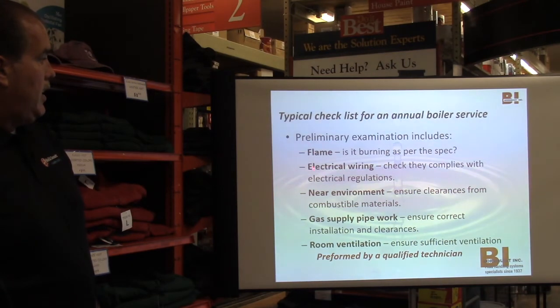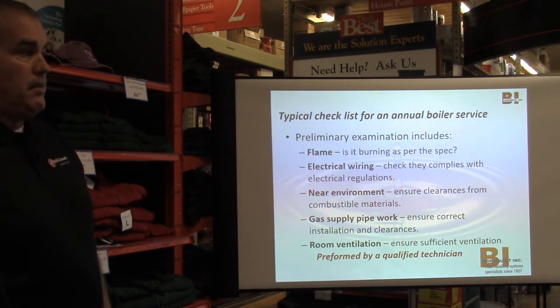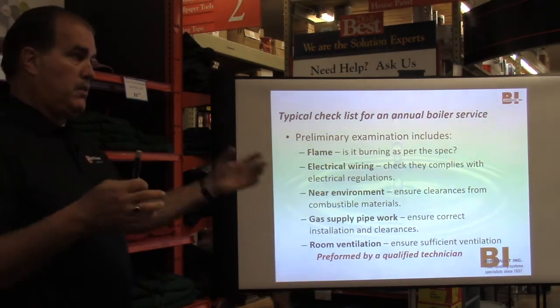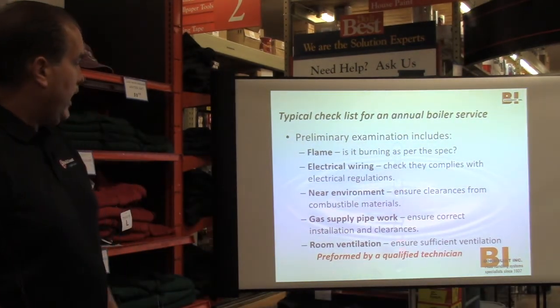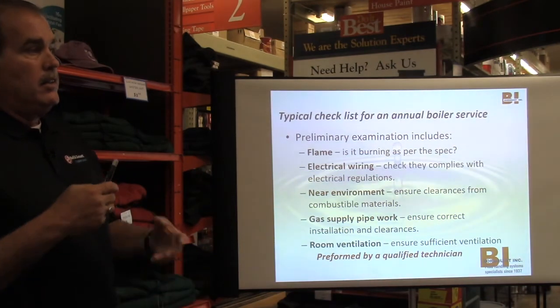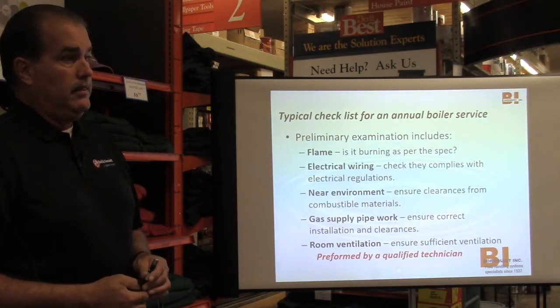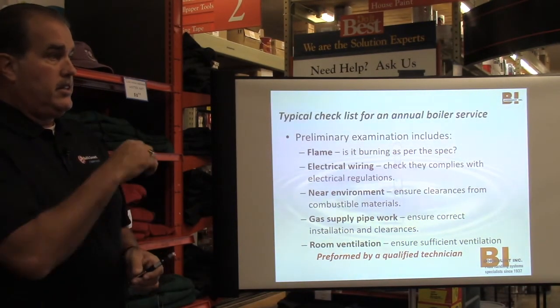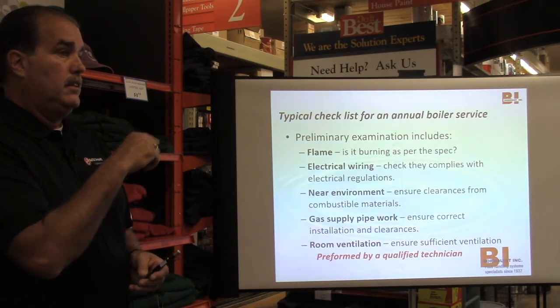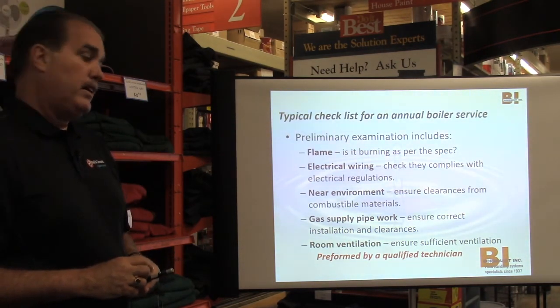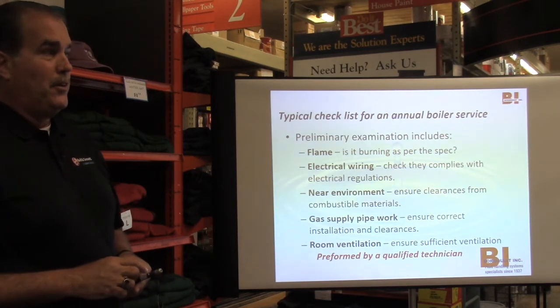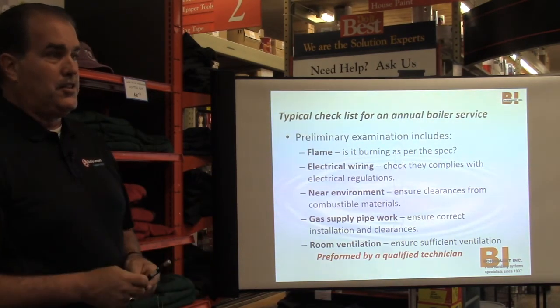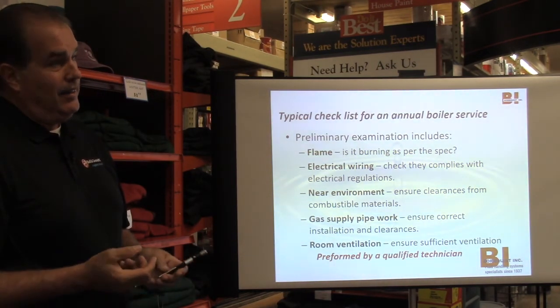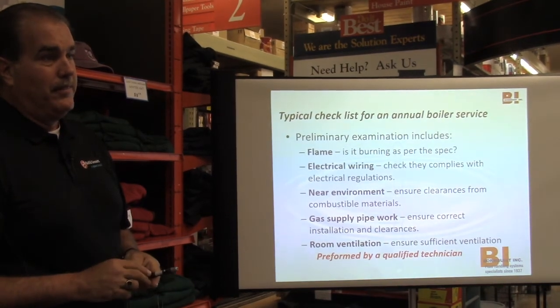He's going to be checking your flame. He's going to be checking your electrical wiring. Obviously, he's going to check to make sure that there are no combustibles near the piece of equipment. Gas piping, room ventilation. These are all things the guy should be looking at, because if he knows this can affect combustion, he'll look for it. If he's just going to walk in and walk around your boiler, turn it off, and maybe blow some of the heat exchanger out and call it a tune-up, well, you're getting what you paid for.